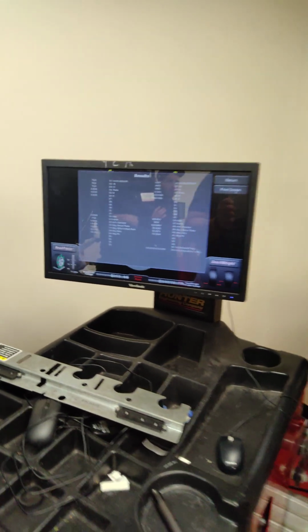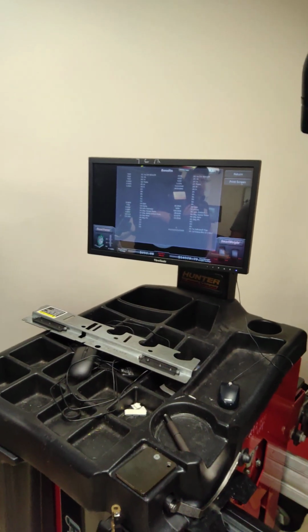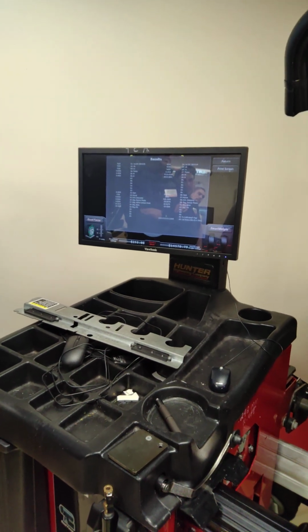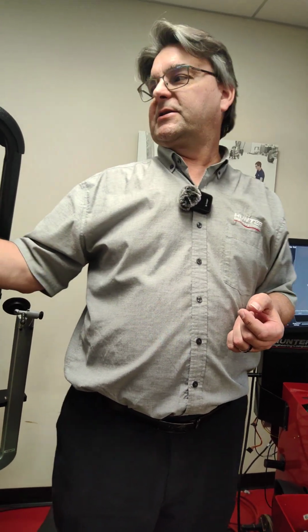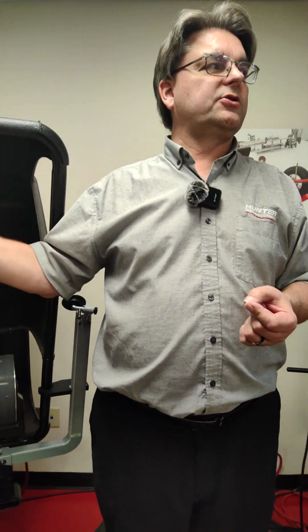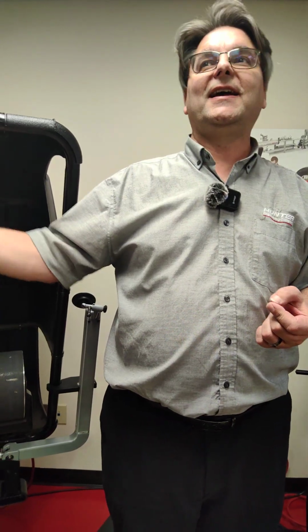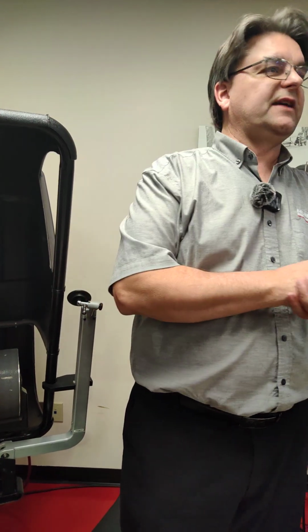When you're in service mode, a wonderful big red error message is going to pop up that says calibration failed, stored due to service mode, because we need to know why it failed. If you can't figure out why it failed, you can't diagnose anything, you can't ever fix anything. So the error message popped up on the screen, and then it said to show calibration error, and then you can show something that's called calibration data. So we're in calibration data right now.